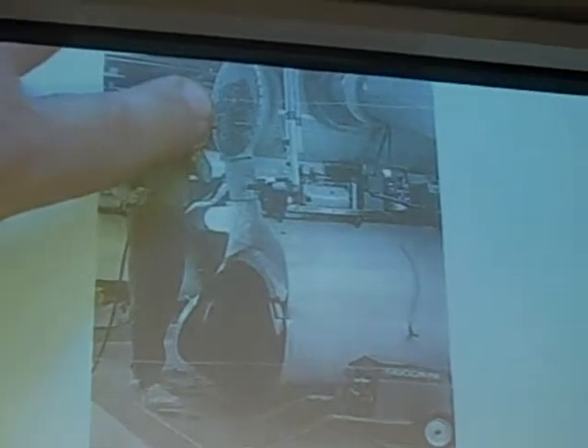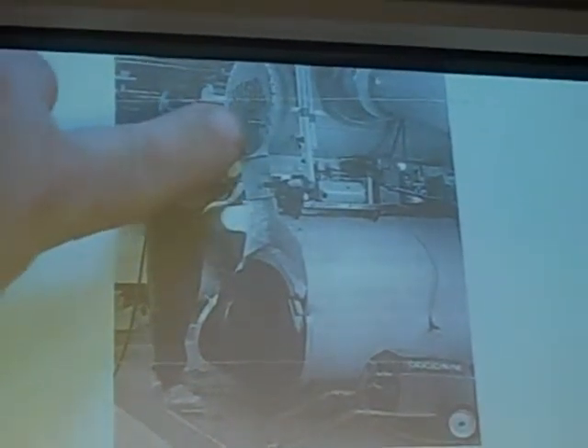You can see all these little tiny holes right there. That's where the water is flowing through those holes. So there's a bunch of little tubes in there. Water flows through those tubes. The outside part of the big tube has the refrigerant flowing in it. So the refrigerant flows across the tubes with the water in them.